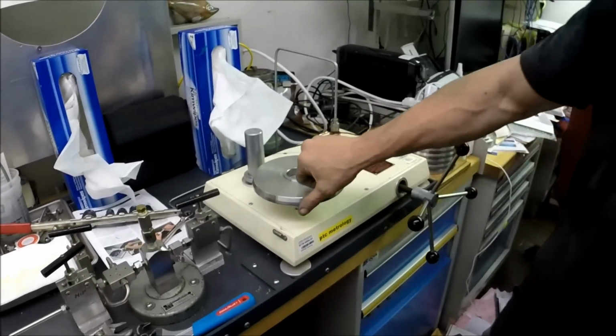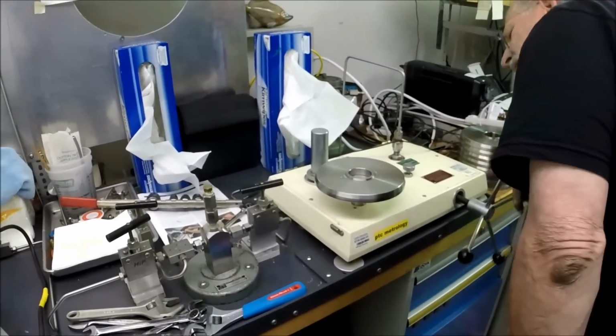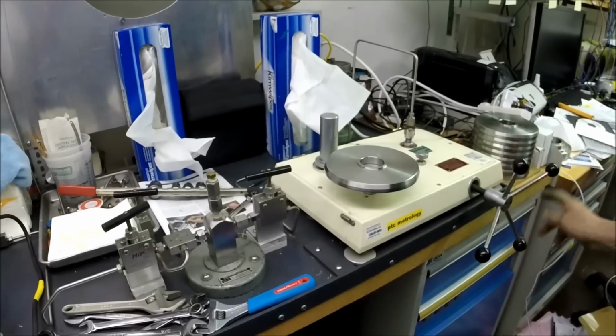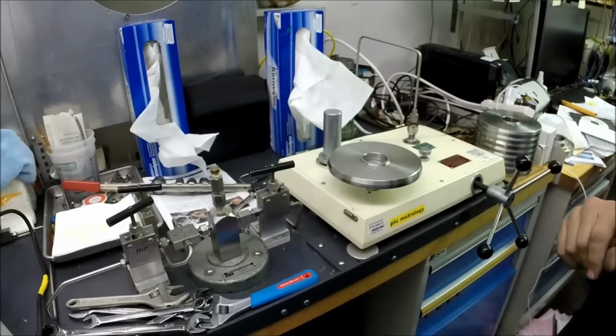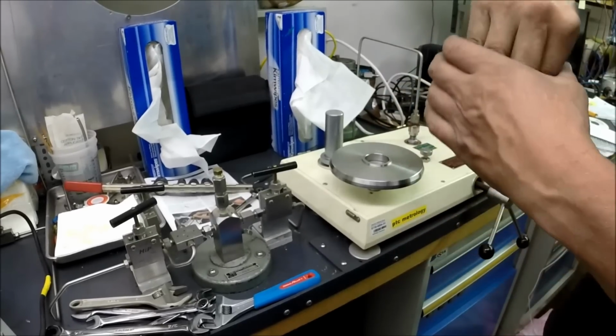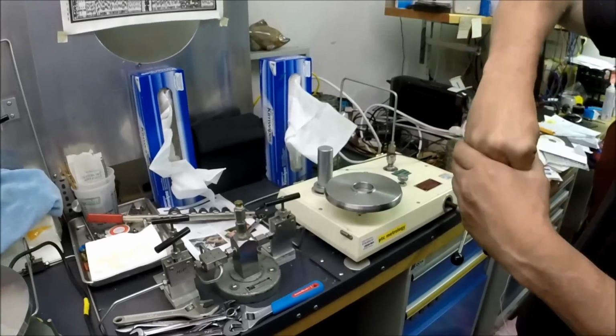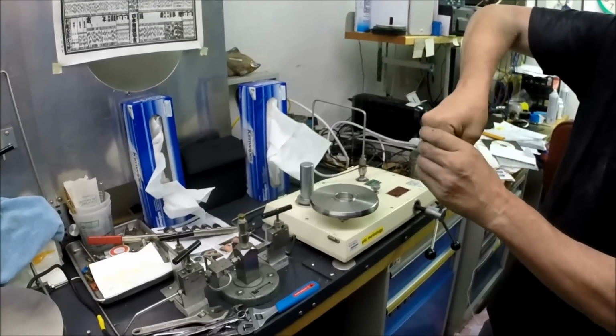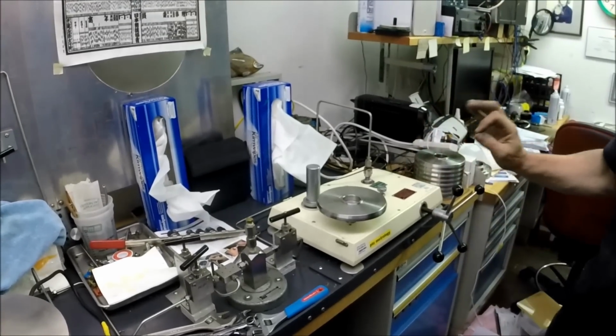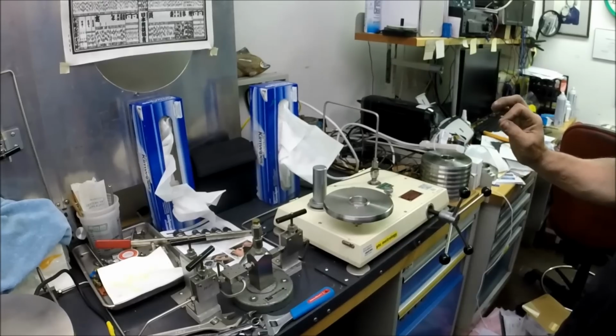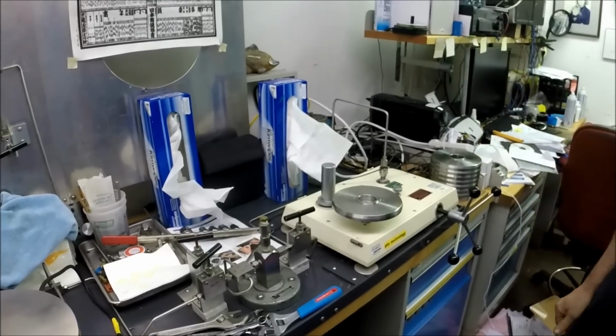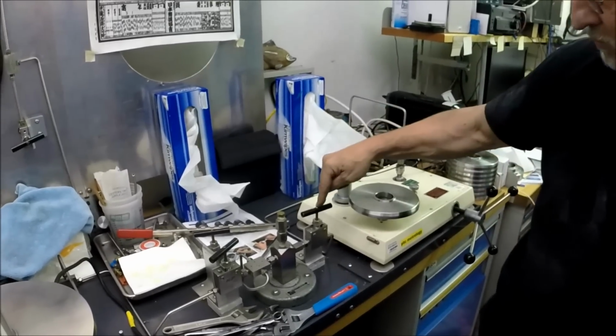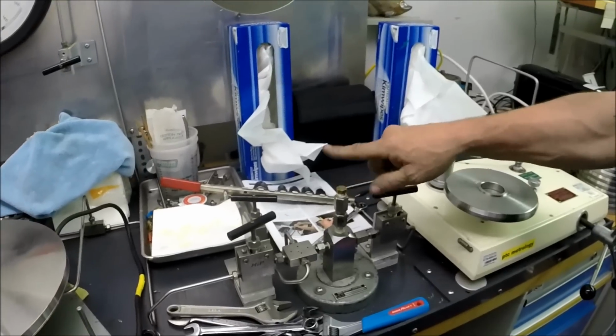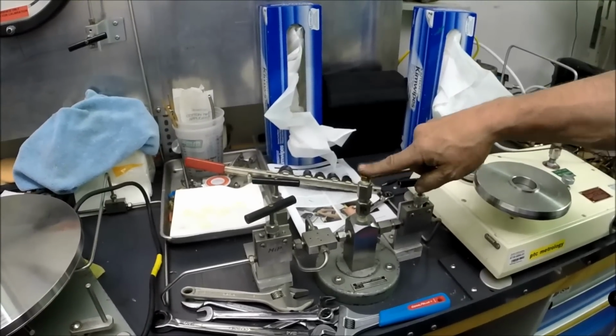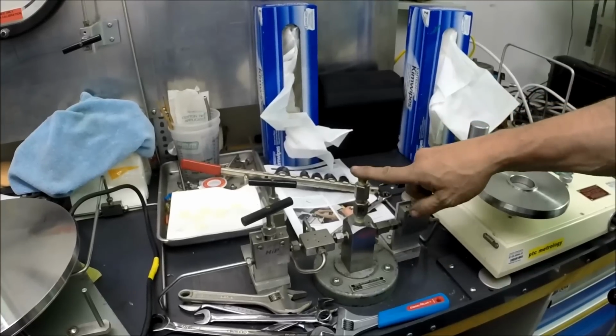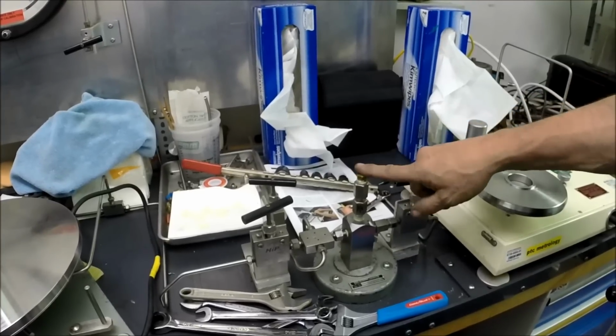You fill it with hydraulic fluid. Once the plate is floating, and you can control that with the hydraulics, you are now generating 52 psi. The rotation keeps the piston and cylinder from locking in a vertical motion. That slight rotation, there's a minuscule amount of oil that's on the piston wall, and it all flows. That pressure would go through this valve to this test station, and you would put your pressure gauge that you want calibrated here. Now, it could be a digital or a mechanical, whatever.